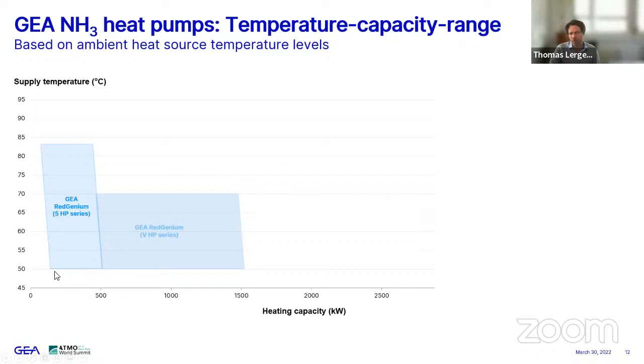It basically just means that when you are looking for higher supply temperatures, in the region of approximately 80 degrees Celsius, with the same compressor size and the same heat source temperature, your available capacity becomes a little bit smaller, the higher you go in your required supply temperature. So that's why these areas are just a little tilted. These are two examples for piston heat pump applications.